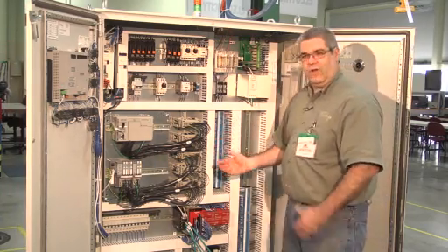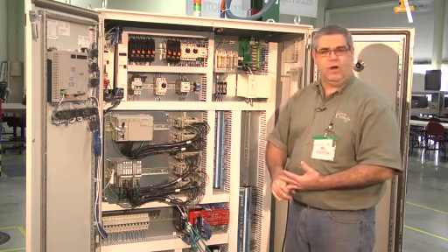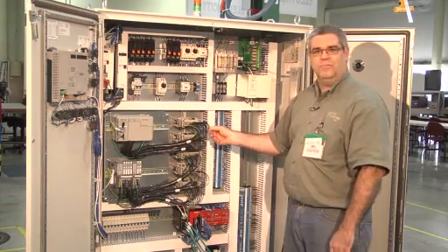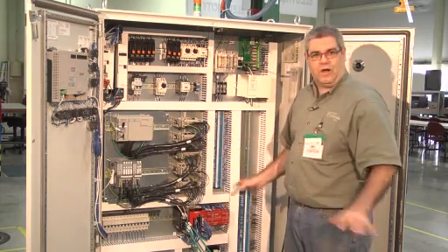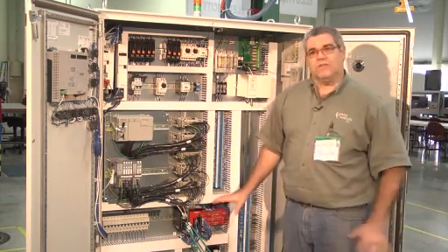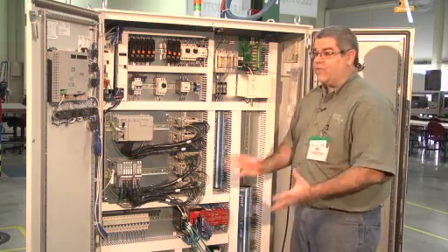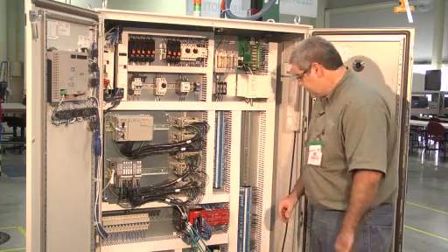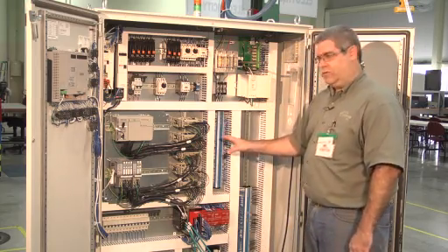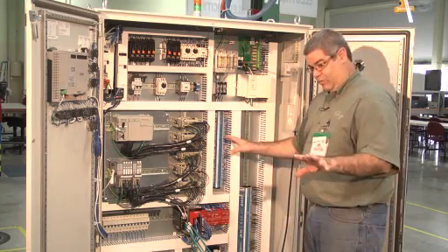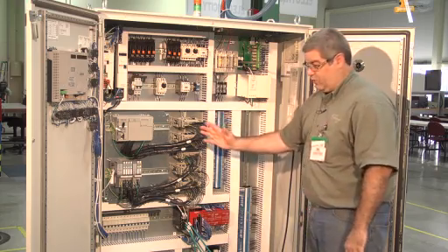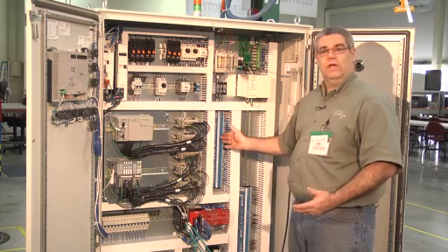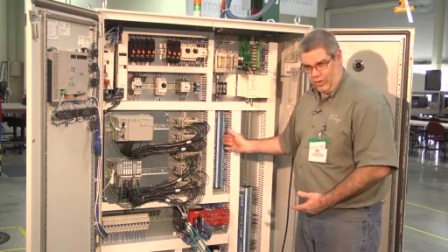You have colored wire, we have THHN, we have MTW wire, we also have color-coded wire, we have cables with numbers on them. So there's a variety through the entire machine assembly system here that has different brands, it's all different. So you can see a variety. The wiring is also done, besides the wire jumpers, it's also done different. If you get in a habit of going from here to here as you're troubleshooting, you're eventually going to find some that don't go here anymore.